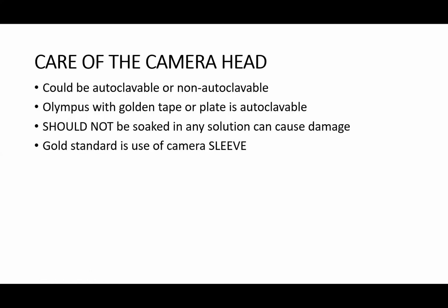That is, you have to take serious precaution. They should not be soaked in any solution, because this can cause damage. Now, camera heads are not soaked in solution. If they are non-autoclavable, you have to clean them with disinfectants for a high-level disinfection. Now there are some sprays we use for high-level disinfection, like the Cidex spray. You can spray and allow for 10 minutes, then you clean off the Cidex, or you can use ammonium to clean. Okay. But the gold standard is to clean, then you apply a sterile camera sleeve. There are long polythene transparent bags that come in a sterile manner that are sleeved over the camera head and the cable. So the surgeon will be handling the sleeve rather than holding the camera directly. So that is the gold standard.